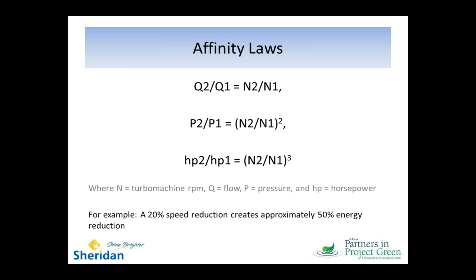If I change my speed by half, I should expect my pressure to go to basically 1/4. So I'm dealing with the squared relationship. And likewise on power, my ratio of speed cubed is going to tell me about my power reduction. So if I've done a half reduction in speed, I'd expect my horsepower consumption to be 1/8 of what it was originally. So I've managed to make huge savings in horsepower just by a simple half reduction. And we saw that in the graph with the variable speed drive, that a 50% reduction in flow was bringing me down to about 20% consumption.